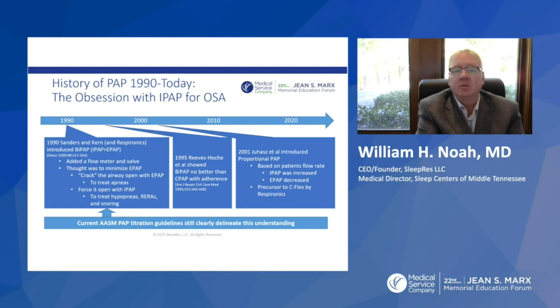In 2001, they introduced proportional PAP, where during IPAP, the pressure was increased, and during EPAP, the pressure was decreased. And this is the precursor to C-Flex by Respironics 2 years later. And again, in 2003, they introduced C-Flex. ResMed later introduces EPR. C-Flex is flow-based. EPR is basically just a simple BiPAP. The pressure just drops on exhalation, whether 1 to 3 centimeters, depending how you set it.